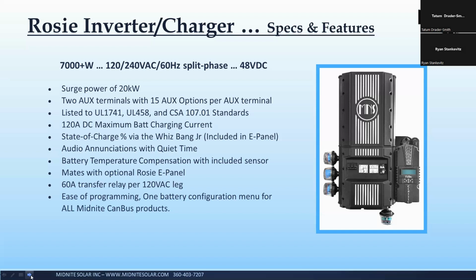And the same like with the Rosie, you can just keep adding Rosies. Stacking, we're talking about probably 10 is going to be the limit on the Rosies. Right now we're supporting 2, but engineering is gearing up to start testing 6 in parallel. And basically the way that works, it's very similar to like the Schneider systems, or the old Outback systems, where the primary Rosie will basically monitor what everybody's doing and the loads. And if you get a big load that comes on, it will turn on all the secondaries or the followers, whatever terminology you want to use there, and it will power that load, and then it will start dropping them off. So if you have, say, 4 Rosies, that's 28 kilowatts of power. And if you turn on a 10 kilowatt load, the first Rosie is going to turn on the other 3, and then when it sees it's only 10 kilowatts, it's going to turn a couple of them back off.